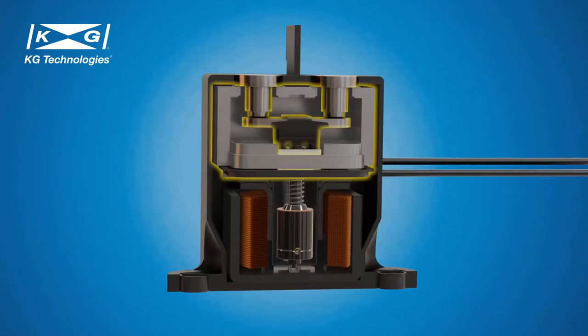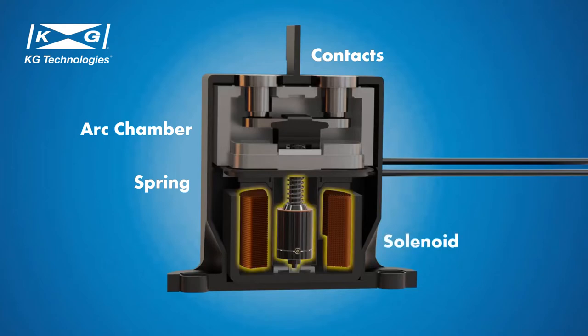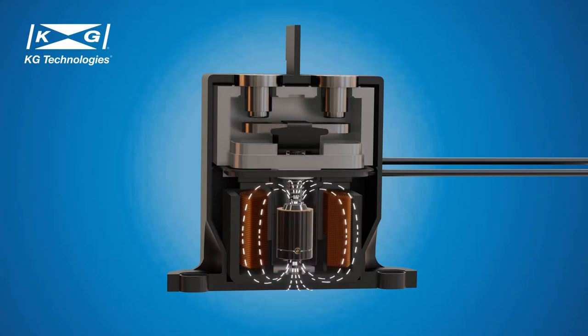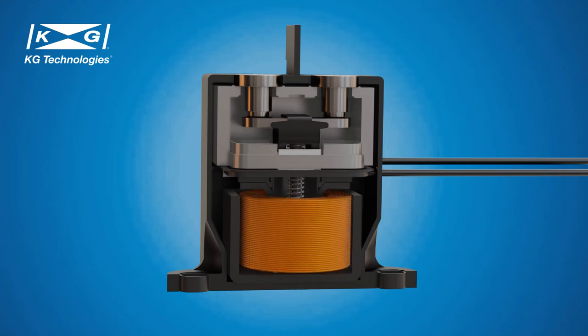The ceramic sealed HVDC contactor contains a ceramic sealed arc chamber, contacts, spring and solenoid module. When the control current flows through the coil of the solenoid, it generates a magnetic field and pulls the bottom part of the contacts to close the main circuit. The ceramic sealed chamber is filled with hydrogen, which is the best arc extinguishing gas. The hydrogen ensures quick arc extinguishing, allows contactors to make or break higher voltages, and ensures stable contact resistance in harsh environments.